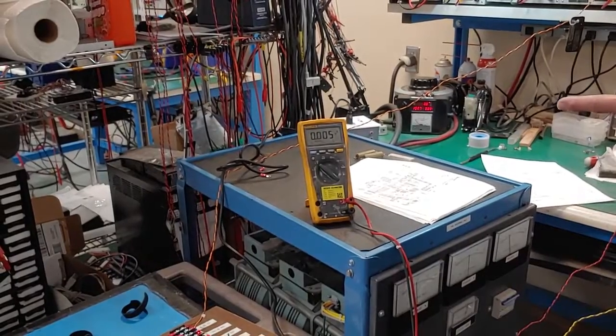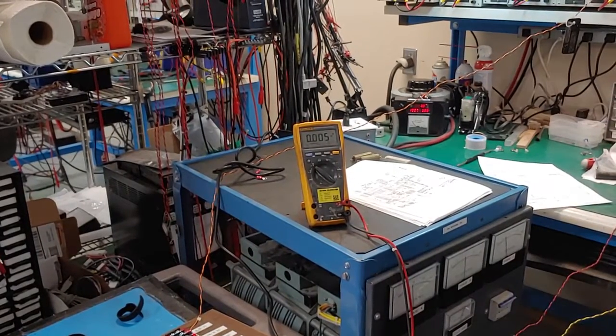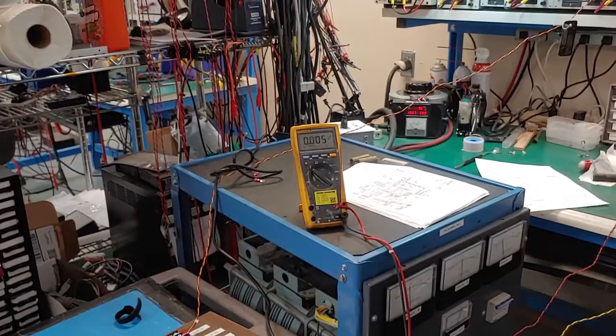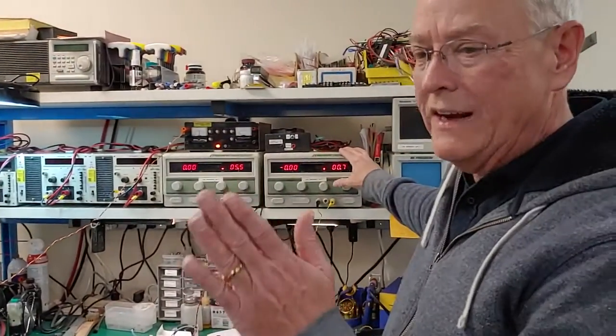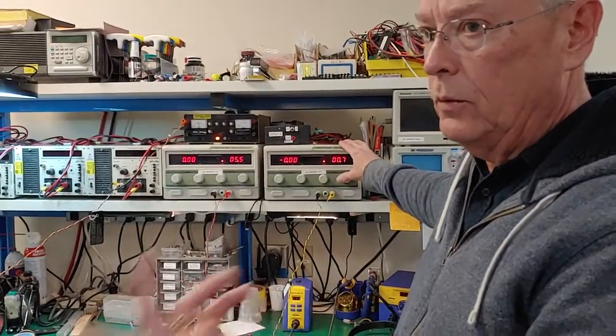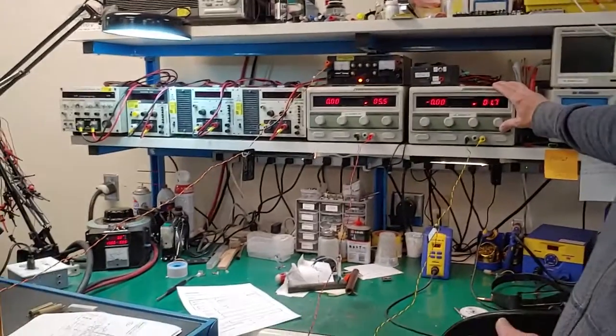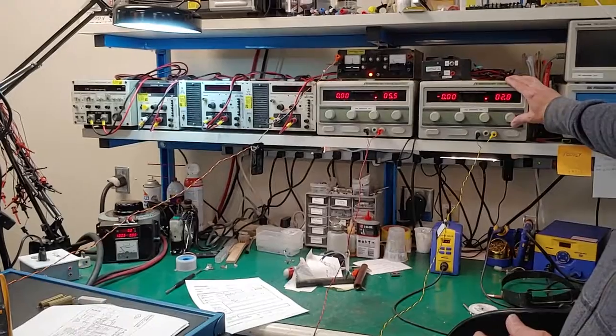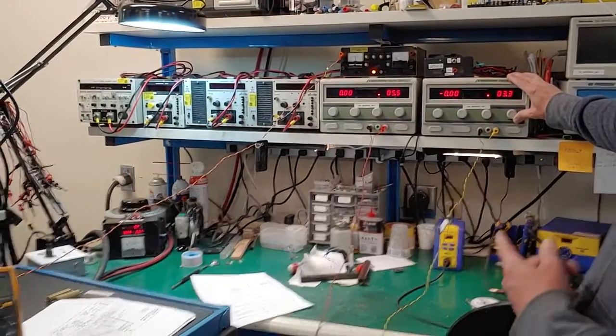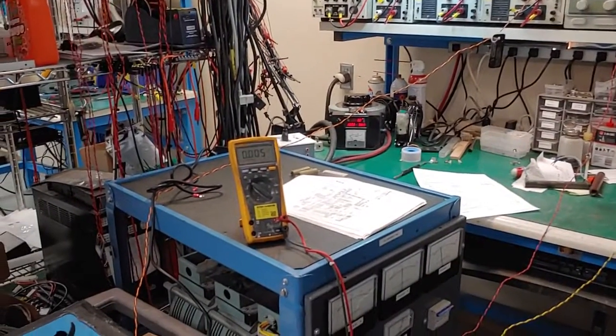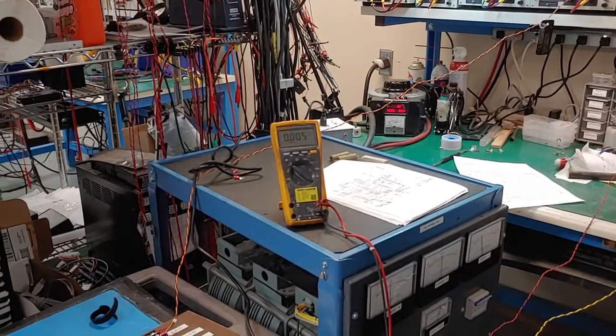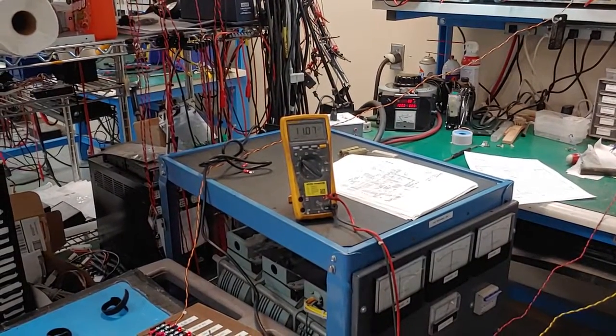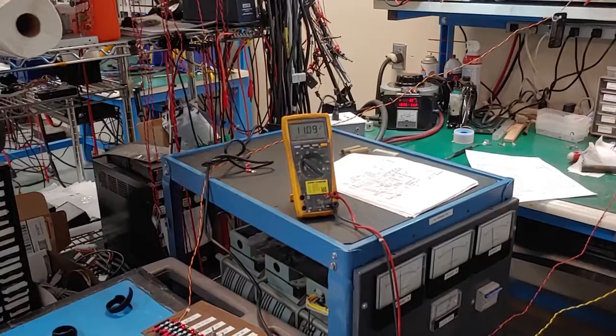We should see that switch and turn on the filaments. Again, if this was closed loop, it would actually regulate, but there's no regulation here because we're open loop. I'm going to increase this. When this gets up to about 3.7, I should see it change over. So we're sneaking up on it right now. 3.5, 3.7, there you go. So at 3.7, I've now asked it to do that.